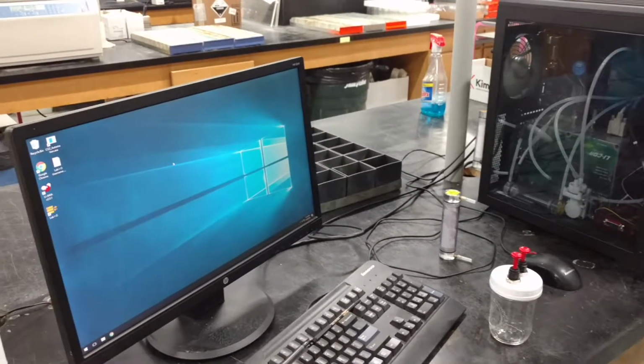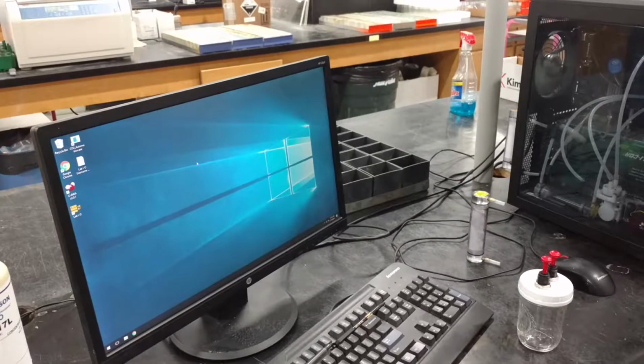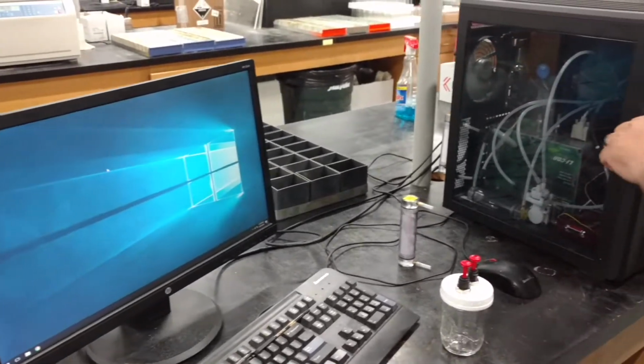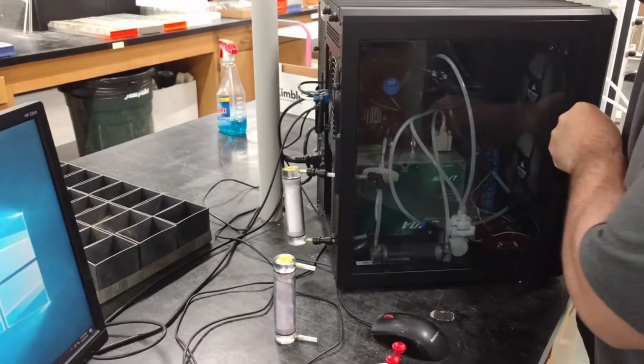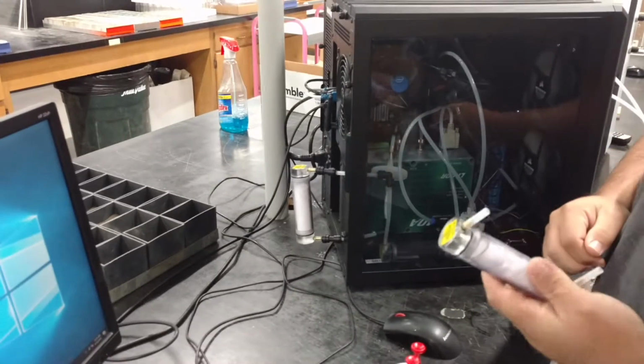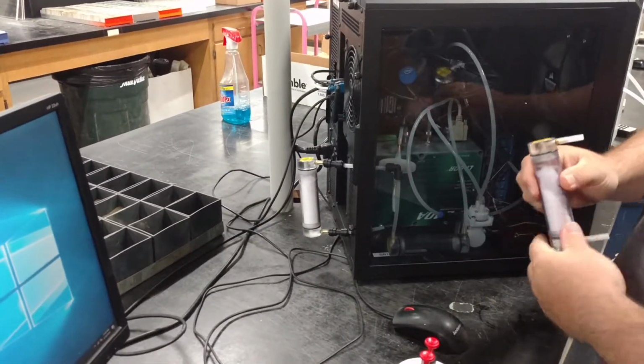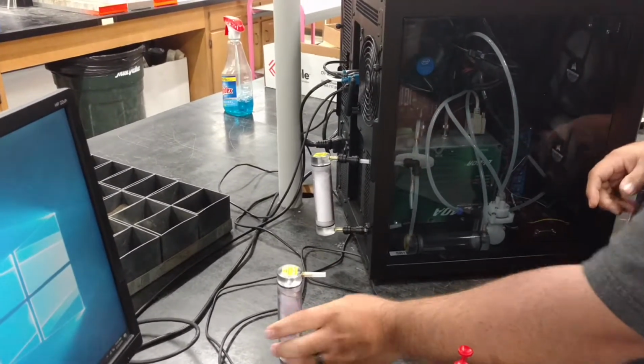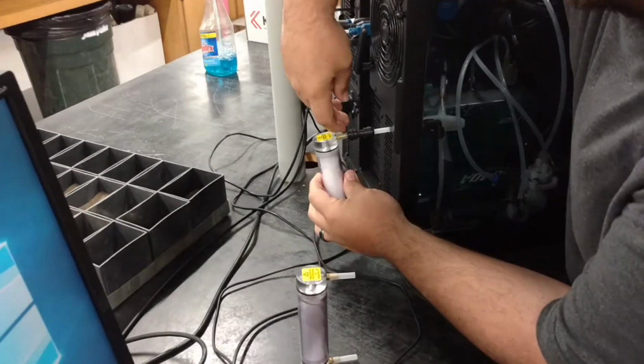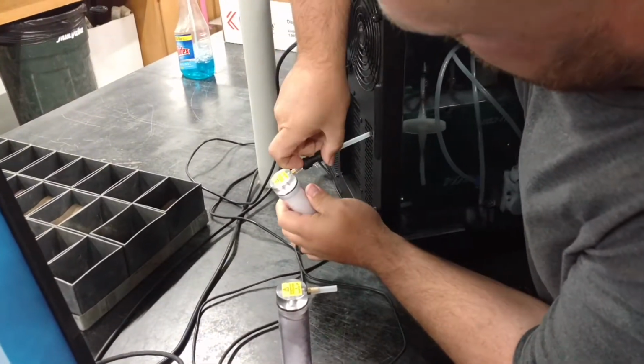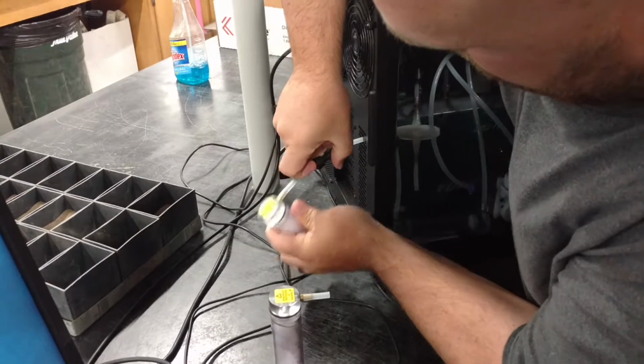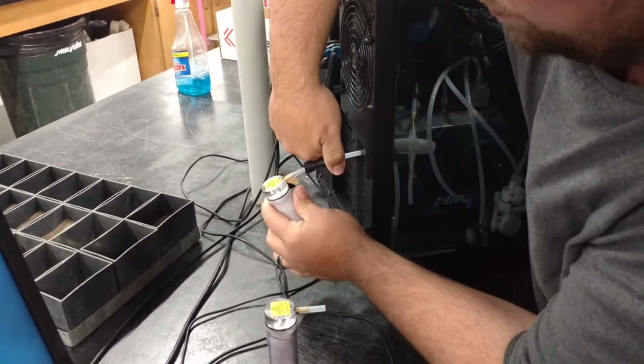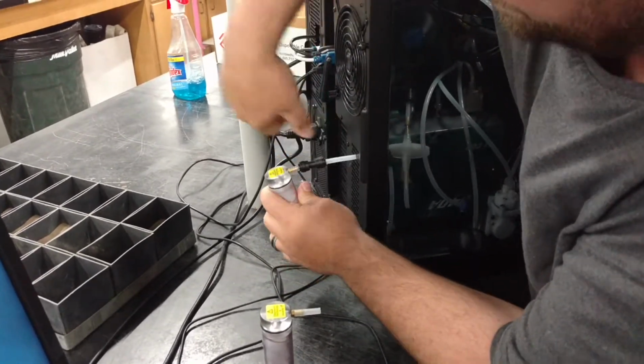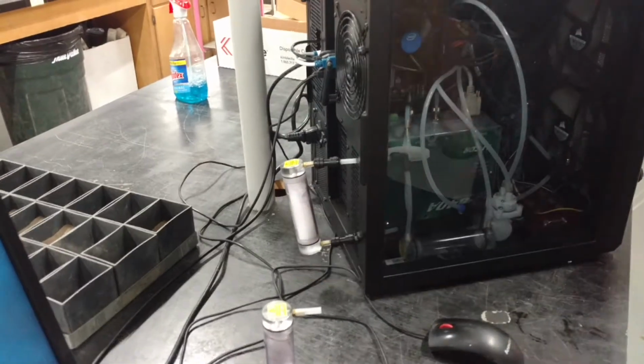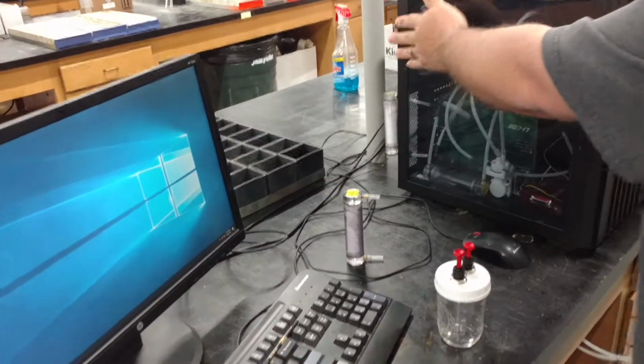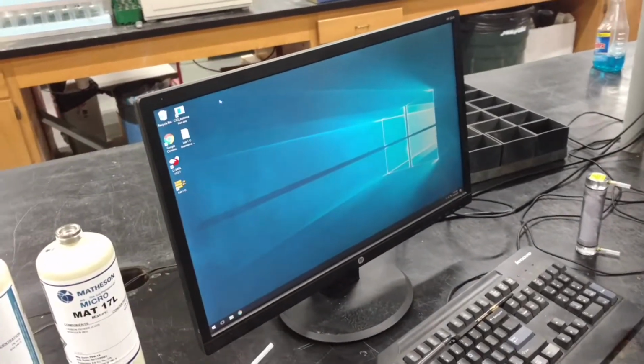Today we're going to show you how to calibrate your SR-1 instrument. This instrument's been powered on for about 10 minutes and is at operational temperature. To begin, we're going to swap out the desiccant tube located on the back of your SR-1. We've already done this with a pre-packed column, but we'll show you how to do it here. Simply press on the quick connect coupler to remove the old desiccant tube. Make sure that all of your fittings are tight after replacing the column before moving on to the next step.